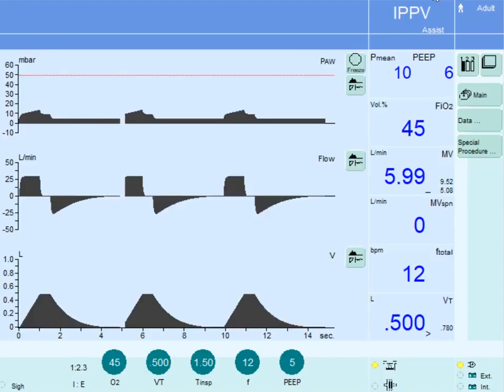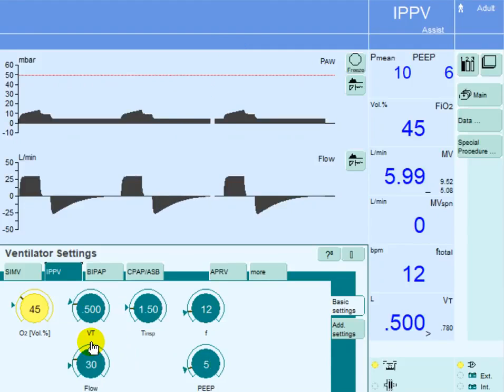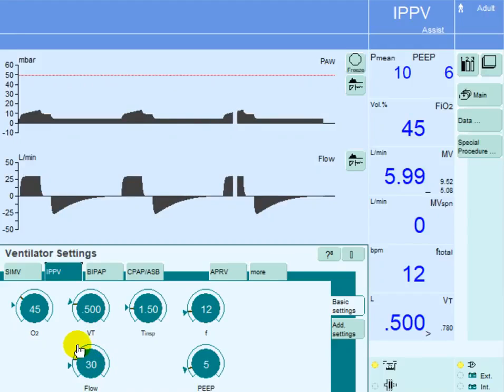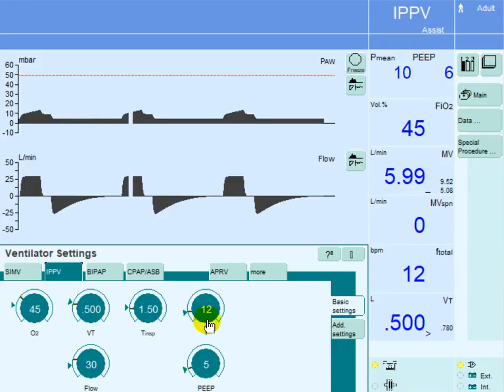In assist-control mode of ventilation, the ventilator settings include, beside FiO2, the target — which could be volume or pressure. In our example here, it's a volume; we're targeting to deliver 500 ml of air into the lung, and this will be delivered at a flow rate of 30 liters per minute. The set rate on the machine is 12 breaths per minute, indicating that every five seconds there will be a breath.